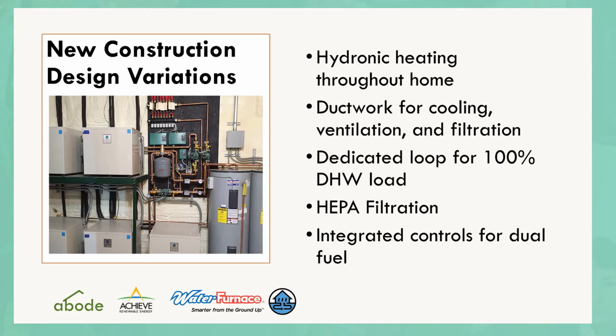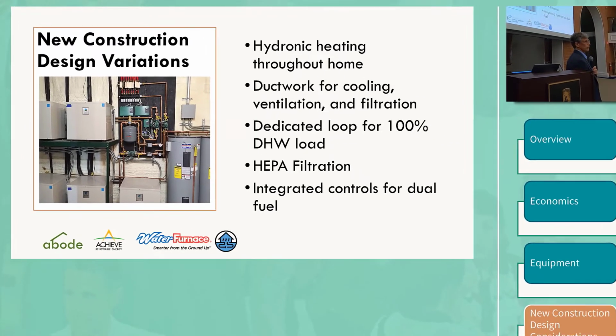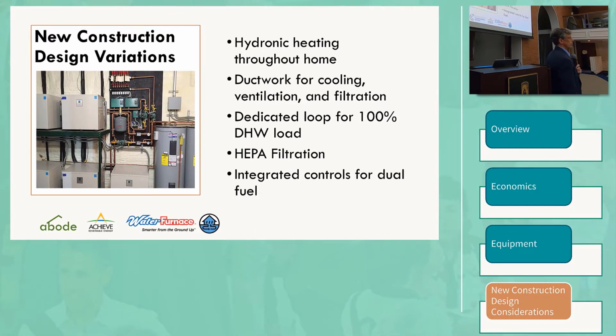You will see references in the literature to ground source heat pumps being used in a dual fuel configuration, where the ground source heat pump heats the structure to a certain point, and then a gas boiler or something takes over. I want to throw holy water on the computer when that sort of thing pops up, because there's no need to have any kind of backup source for a geothermal install.